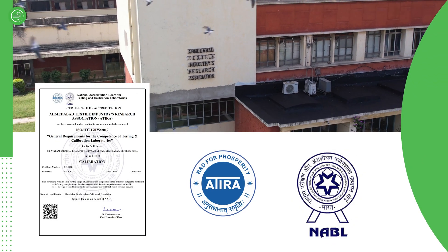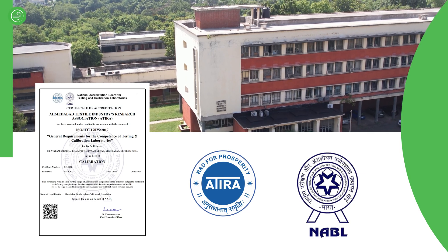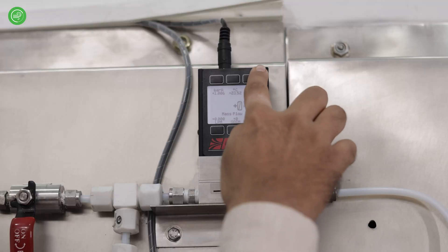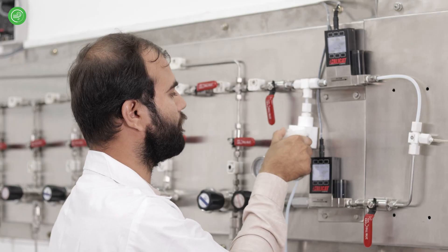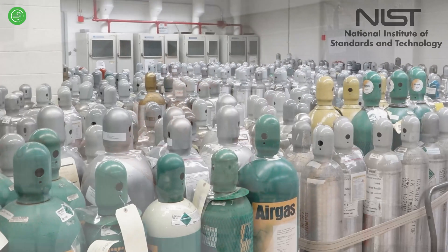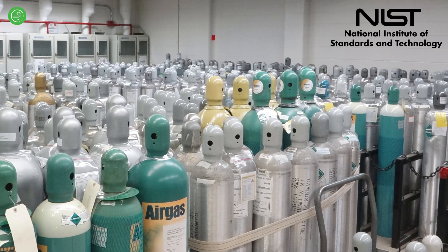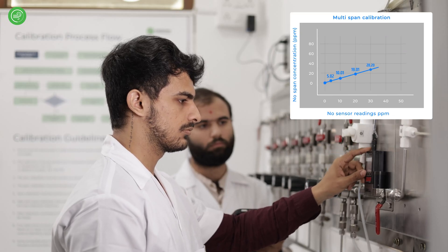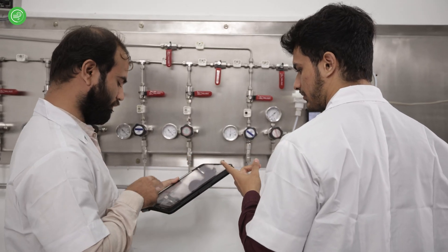OISOM has a state-of-the-art calibration facility jointly developed with ATIRA, which is an NABL accredited ISO/IEC 17025 certified environment laboratory. Each sensor undergoes a zero and span calibration in a clean and controlled lab setting using known concentrations of gases delivered through NIST traceable calibration standards.